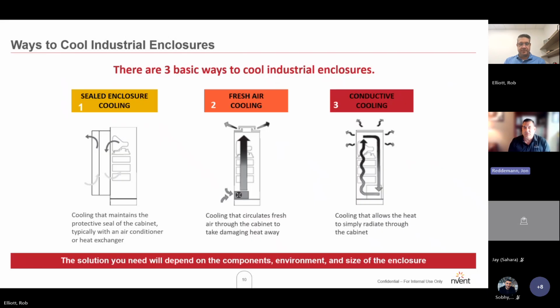When we're talking about cooling an enclosure, there are three basic ways to cool a system: a sealed enclosure, fresh air cooling, and conductive cooling. A sealed system essentially is just that: the enclosure air does not interchange with the ambient air at all. It just simply recirculates inside the enclosure. Fresh air cooling is literally using the fresh air like a fan and filter system, and we're pushing it through the box, whether we push it through or we pull it through in a vacuum. There are different reasons based on application why we would do one over another. But essentially, we are using our ambient air as our cooling medium to help manage that temperature. And then we have conductive cooling, using the enclosure surface itself to help us dissipate the heat. Thermodynamic law, hot goes to cold, right? So hot will transfer to cold until it can't transfer anymore.